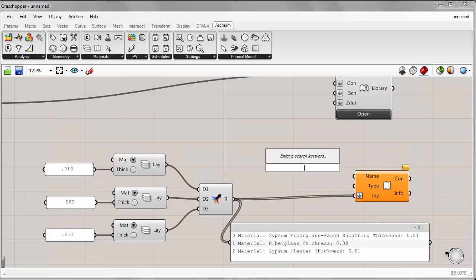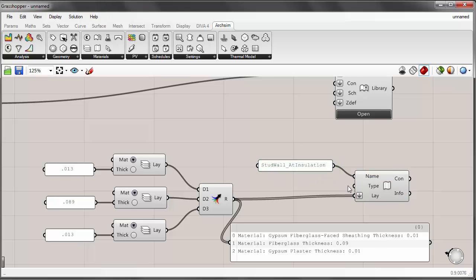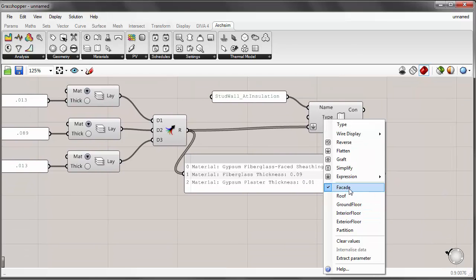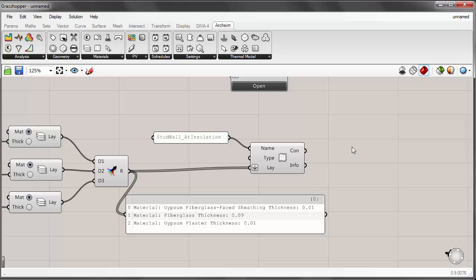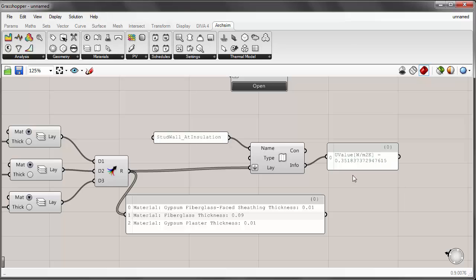Now I can give this a name — I'll call it stud wall at insulation, meaning this is a stud wall taken through the path of the insulation. Under type, we can choose different types of construction, which adds a different heat transfer coefficient for the air films. Since this is a facade, I'll keep it at facade. Placing a panel on the canvas shows the name of the construction and the overall U-factor for the entire assembly — it's 0.35.